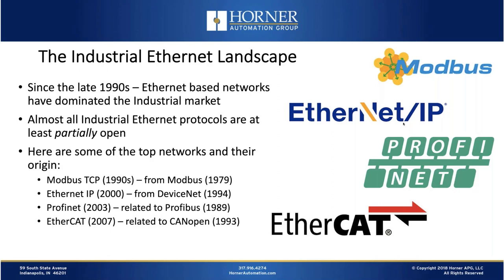Profinet is another big industrial Ethernet protocol. Whereas Modbus TCP is Modbus over Ethernet, and Ethernet IP you can think of fairly accurately as DeviceNet over Ethernet, Profinet is related to Profibus but it's certainly not just Profibus over Ethernet. Similarly, EtherCAT is another protocol you'll find out there, related to CANopen and using a lot of the same messaging formats. So those are the main players.